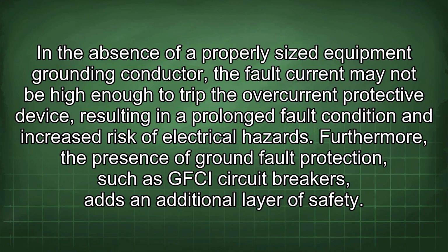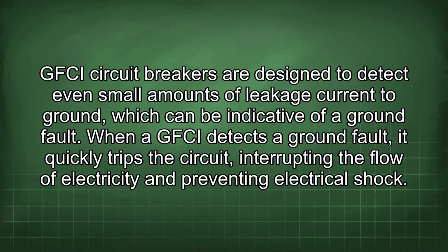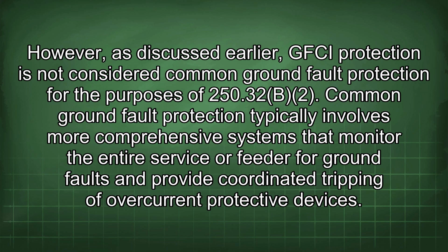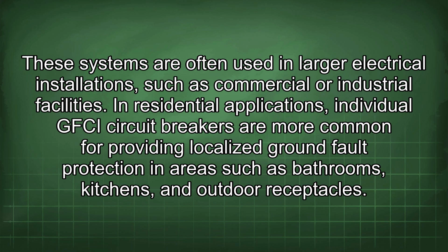Furthermore, the presence of ground fault protection, such as GFCI circuit breakers, adds an additional layer of safety. GFCI circuit breakers are designed to detect even small amounts of leakage current to ground, which can be indicative of a ground fault. When a GFCI detects a ground fault, it quickly trips the circuit, interrupting the flow of electricity and preventing electrical shock. However, as discussed earlier, GFCI protection is not considered common ground fault protection for the purposes of 250.32(B)(2). Common ground fault protection typically involves more comprehensive systems that monitor the entire service or feeder for ground faults and provide coordinated tripping of overcurrent protective devices. These systems are often used in larger electrical installations, such as commercial or industrial facilities. In residential applications, individual GFCI circuit breakers are more common for providing localized ground fault protection in areas such as bathrooms, kitchens, and outdoor receptacles.